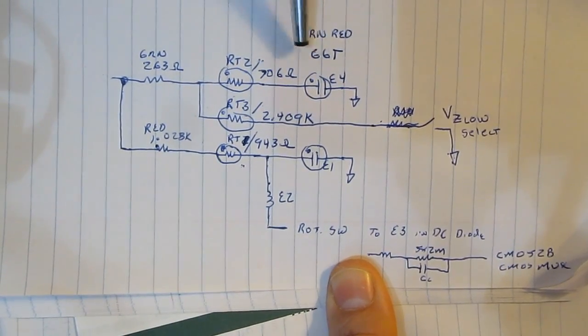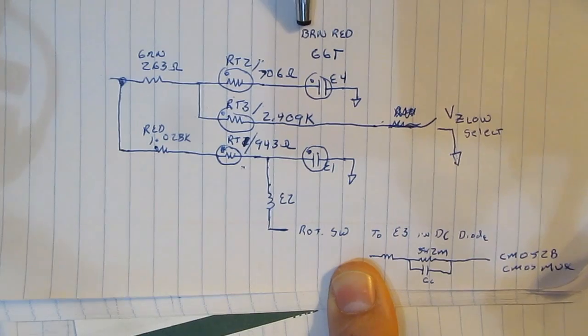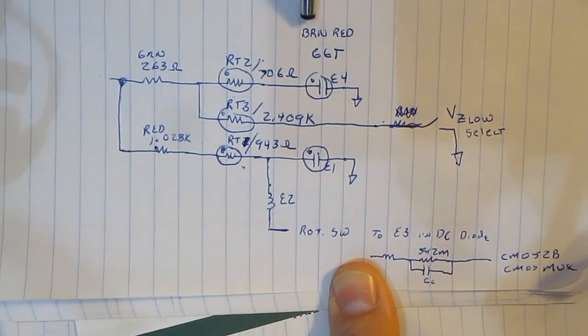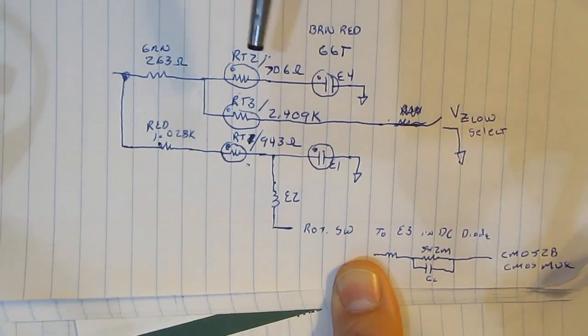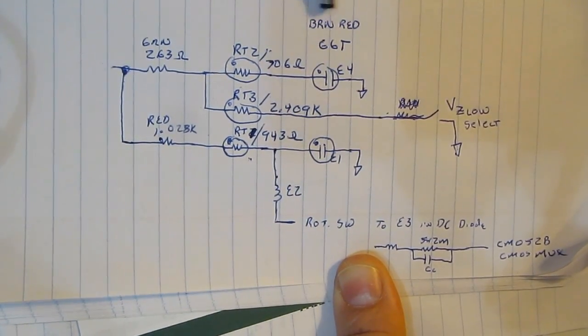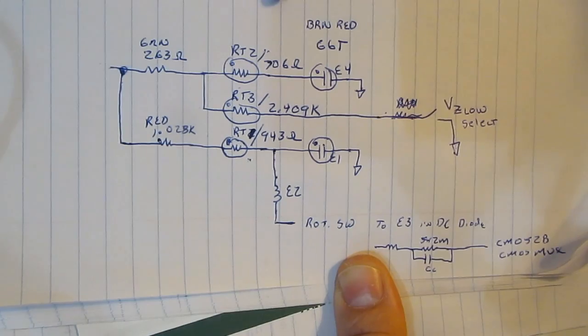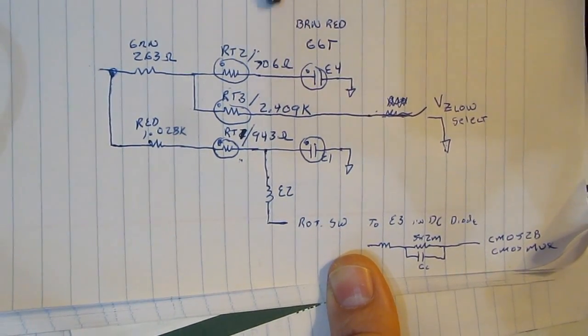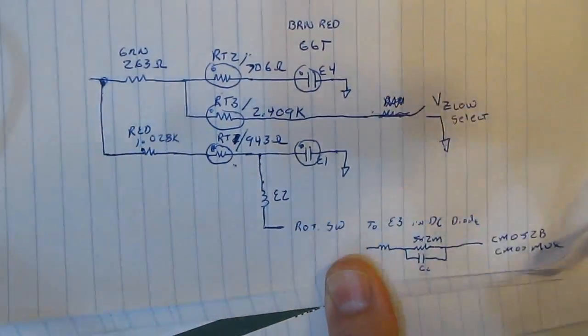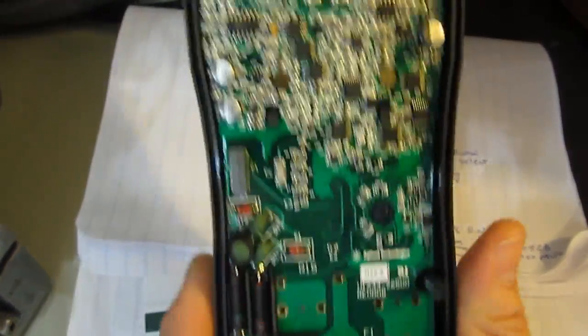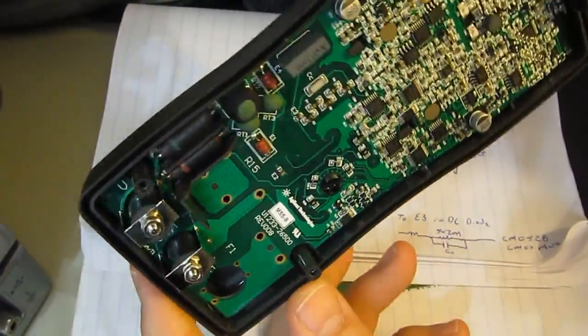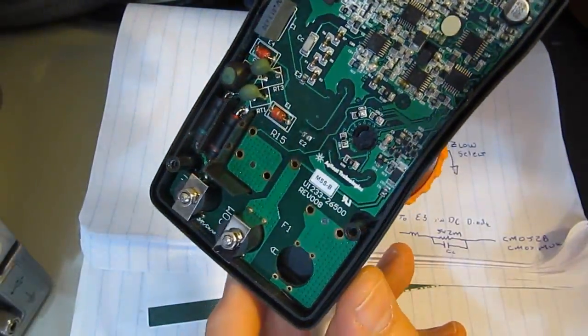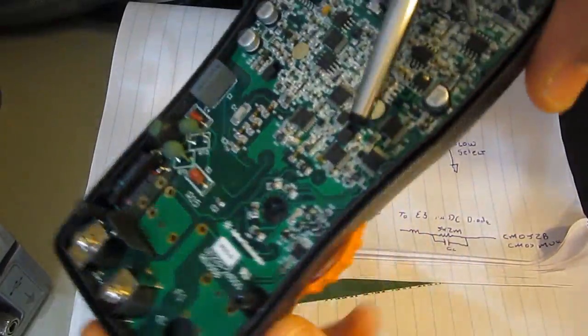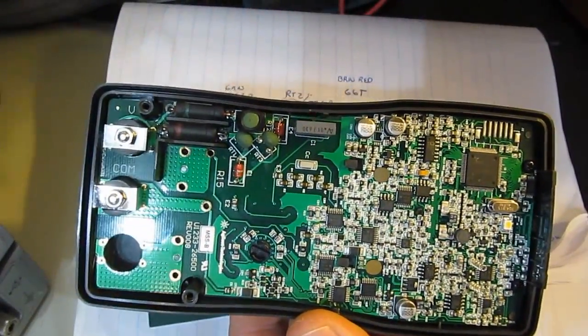RT2 goes back to gas discharge tube E4. Both of these gas discharge tubes are banded with a brown and a red. I assume that brown-red banding means it's a 1.2K or a 2.1K volt part. The thing when looking at the rest of this meter is I don't see any additional downstream protection. So just looking at the meter, again, the level of complexity, how dense this board is, I don't have a lot of confidence, to be honest, that this is going to survive any of these tests. So let me put it back together and we'll do some type of a functional test on it.